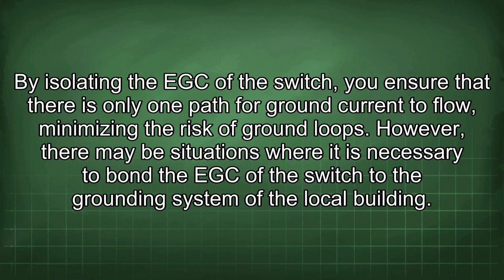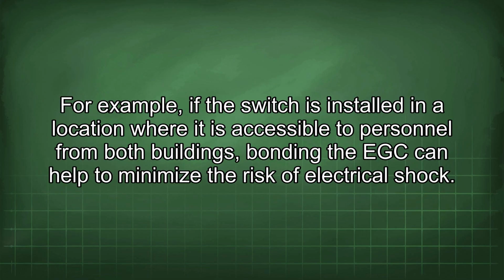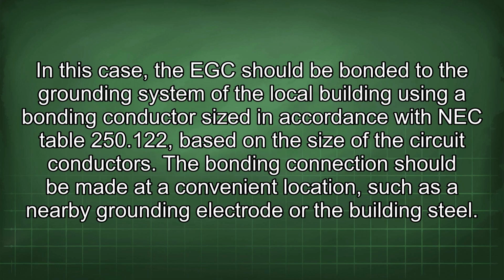However, there may be situations where it is necessary to bond the EGC of the switch to the grounding system of the local building. For example, if the switch is installed in a location where it is accessible to personnel from both buildings, bonding the EGC can help to minimize the risk of electrical shock. In this case, the EGC should be bonded to the grounding system of the local building using a bonding conductor sized in accordance with NEC Table 250.122, based on the size of the circuit conductors. The bonding connection should be made at a convenient location, such as a nearby grounding electrode or the building steel.